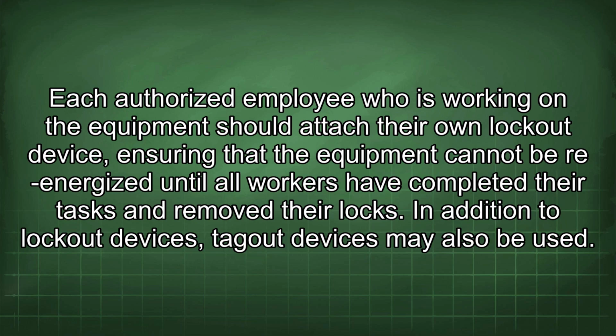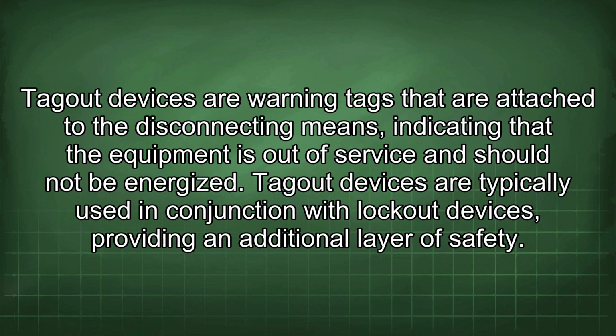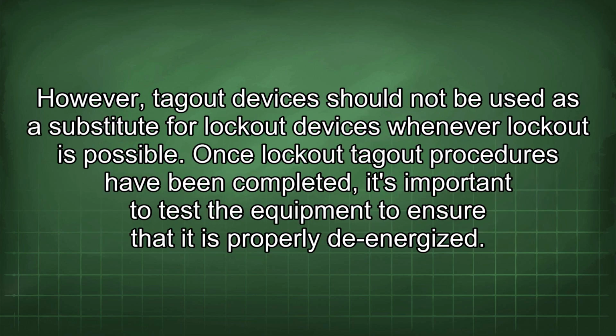In addition to lockout devices, tagout devices may also be used. Tagout devices are warning tags that are attached to the disconnecting means, indicating that the equipment is out of service and should not be energized. Tagout devices are typically used in conjunction with lockout devices, providing an additional layer of safety. However, tagout devices should not be used as a substitute for lockout devices whenever lockout is possible.